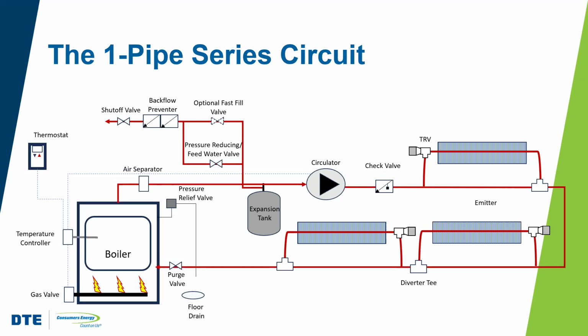And we can see here that, other than the branches here, the system looks pretty much the same as the series system. But this is best with what we call a primary, secondary piping system. So where the boiler is hydraulically isolated. And so here there'd be constant circulation around that main circuit called the secondary loop, which is this loop here, right, where we have our emitters. And then the boiler and the boiler pump, right, the boiler pump here that we've added, would only be running when the boiler's operating, right? So that helps to improve energy efficiency and helps also to reduce losses from the boiler cycling.